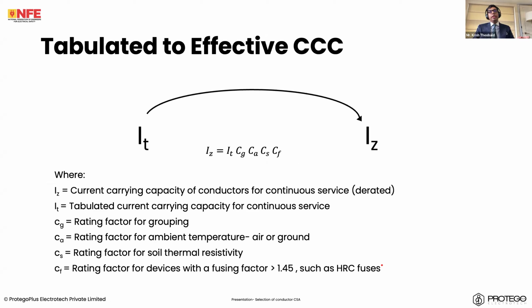Now, the important thing is when we have a tabulated current carrying capacity, as in, this cable can carry this many amps, that is often very different from the effective current carrying capacity, which is the current carrying capacity in continuous service. If we look at the actual factors that come into play to go from IT to IZ, the standard looks at really four factors. Factor for grouping, so how many cables are grouped together. Factor for ambient temperature, whether the cable is in the air or the ground, and what the temperature of the air or the ground is. Thermal resistivity of the soil, how the soil is able to dissipate heat. And the rating factor for devices with a fusing factor greater than 1.45, like an HRC fuse.